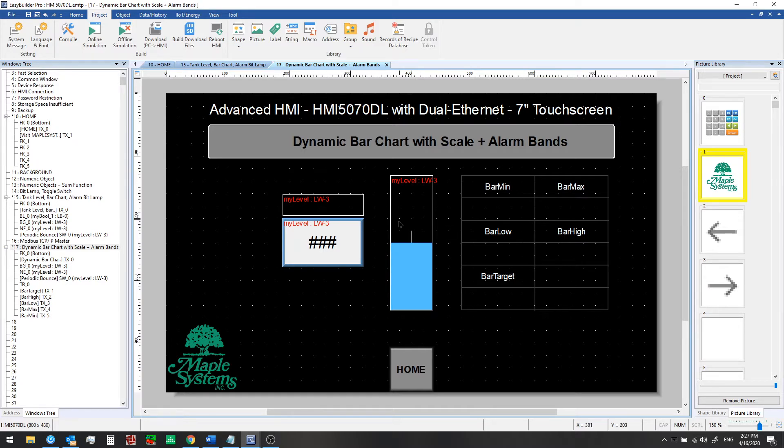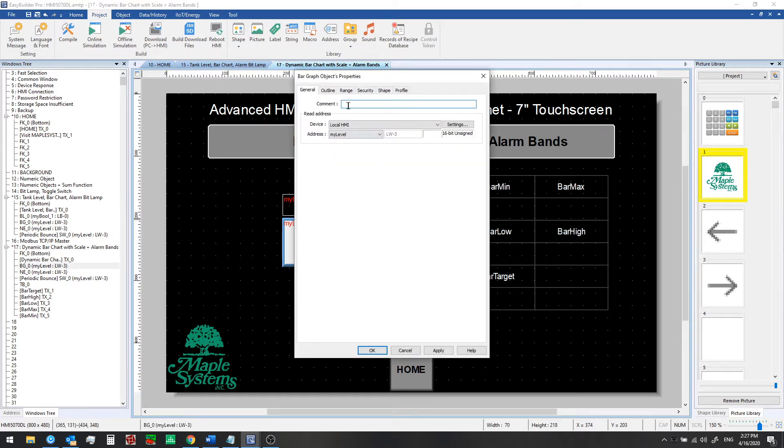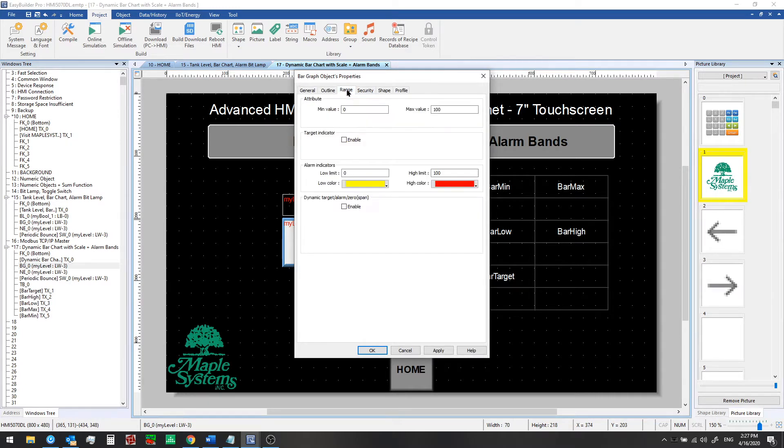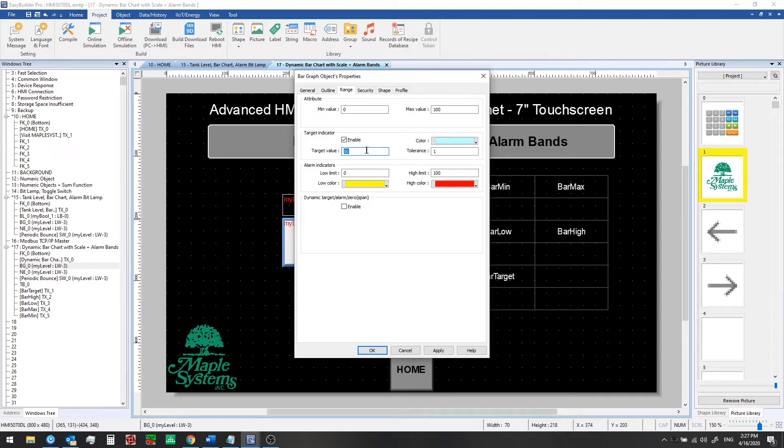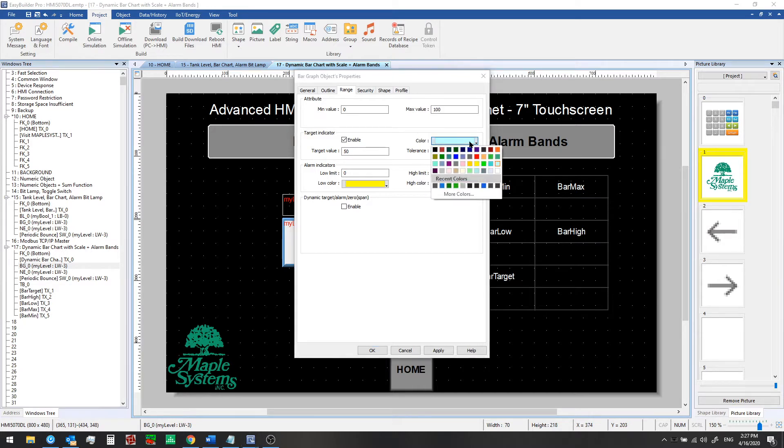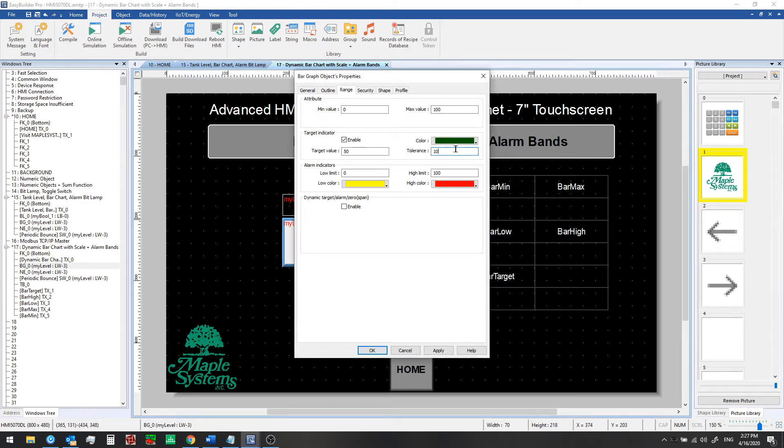To begin, let's look at the settings again in the bar graph properties. Click on the range tab and look at the basic settings here. The target indicator - if we enable this we can set a target value. We'll set it to 50, set the tolerance to 10 so this will again go from 40 to 60, and we'll change the color of the bar graph only in that range. We'll use the dark green color there and then set a low limit of 5 and a high limit of 95.